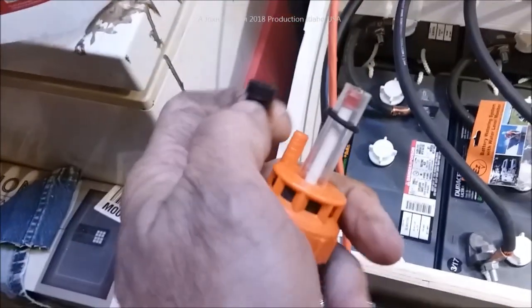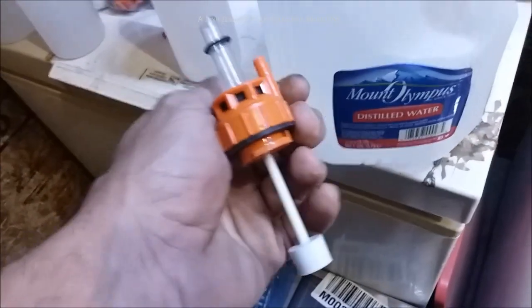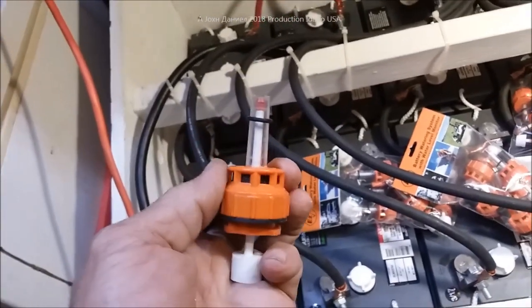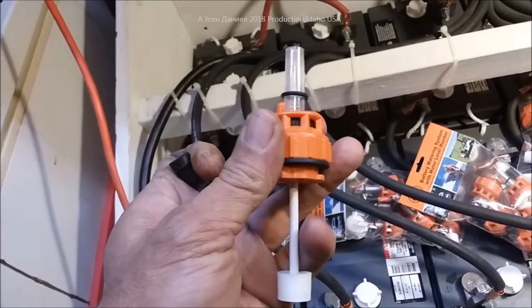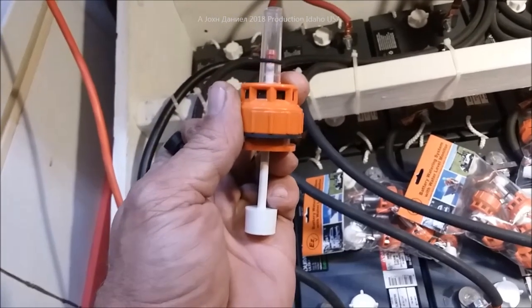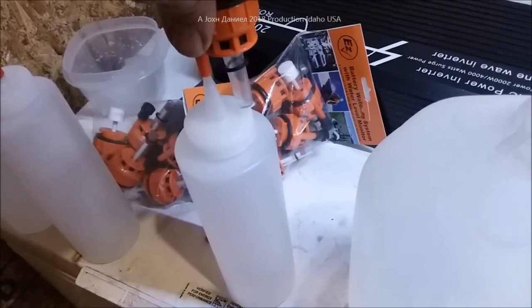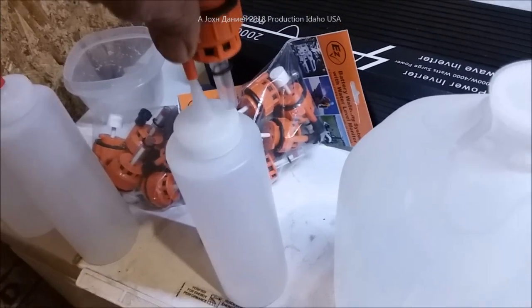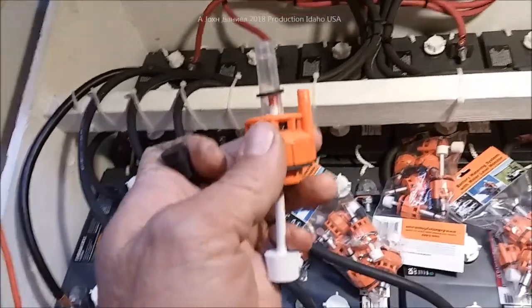The nozzle fits the filling tube on the water gauge. When you buy your battery, you check the water level and then move the O-ring into place. With my batteries I'm roughly three-quarters of an inch below my flood point, which would be about right at the top of the cell, so when I sink below that I know I need water. I can then pull the little rubber cap and add water using the squeeze bottle — they don't really drip when upside down until you squeeze them.